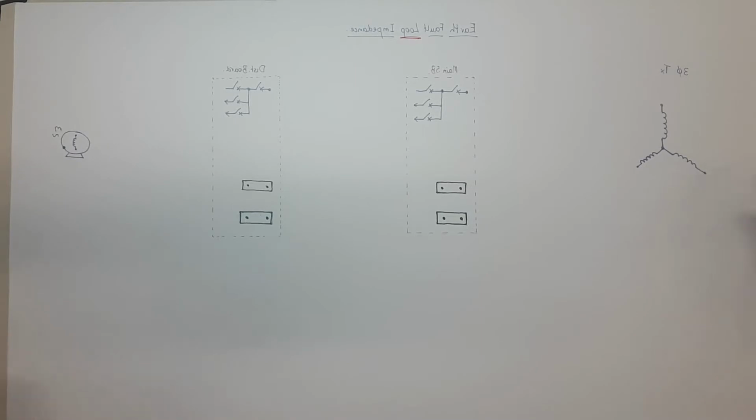So we'll just do a single phase drawing of it, and we'll draw in the loop and trace it out so that for future reference, when you're working out fault loop impedance, you'll have an idea of what is actually being taken into account, because as you know, there are limits on fault loop impedance. We don't want it to be too high.